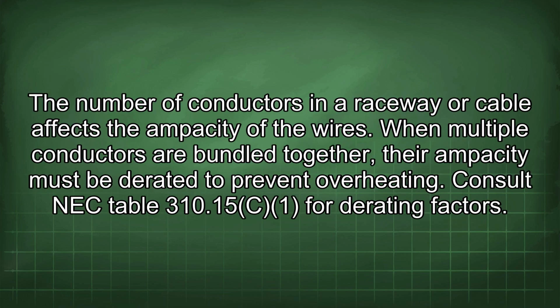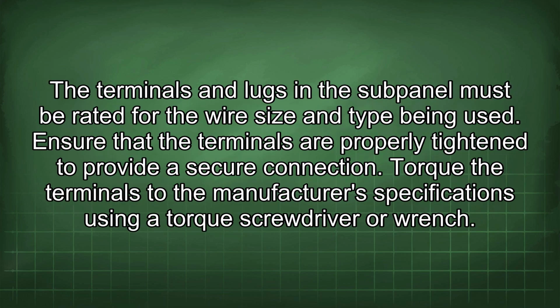The number of conductors in a raceway or cable affects the ampacity of the wires. When multiple conductors are bundled together, their ampacity must be derated to prevent overheating. Consult NEC table 310.15 for current derating factors. The terminals and lugs in the subpanel must be rated for the wire size and type being used.